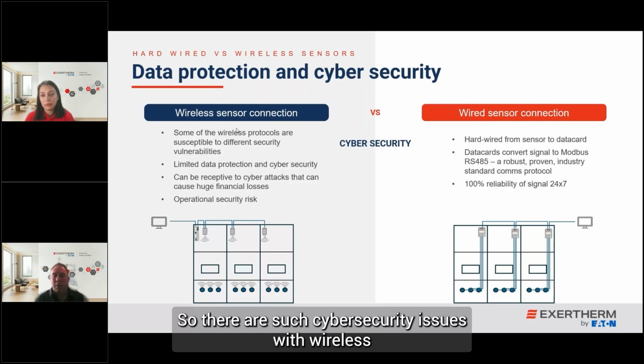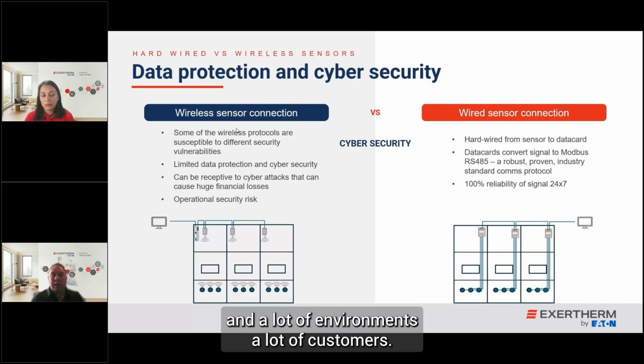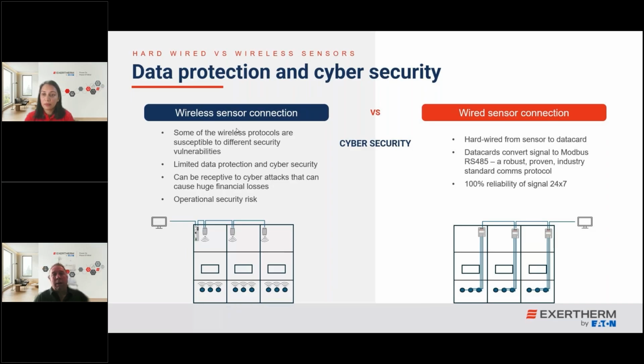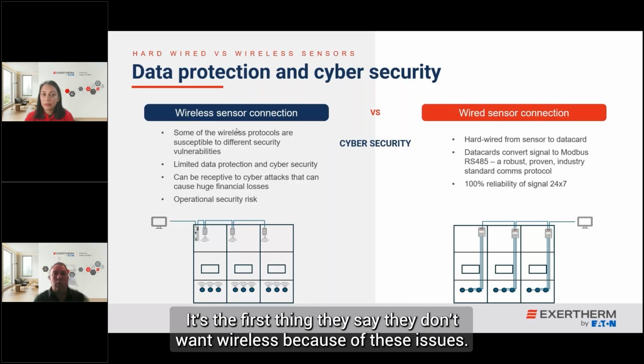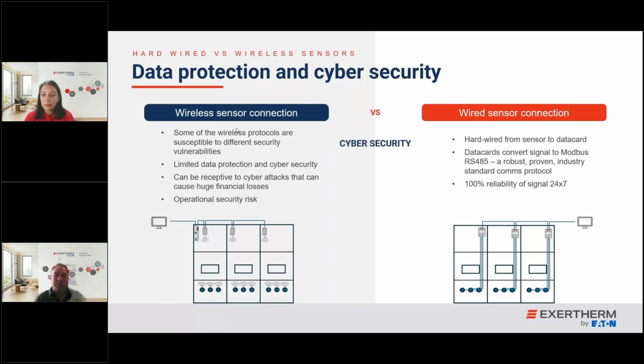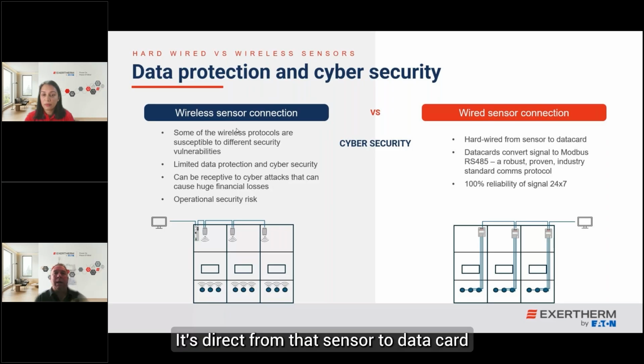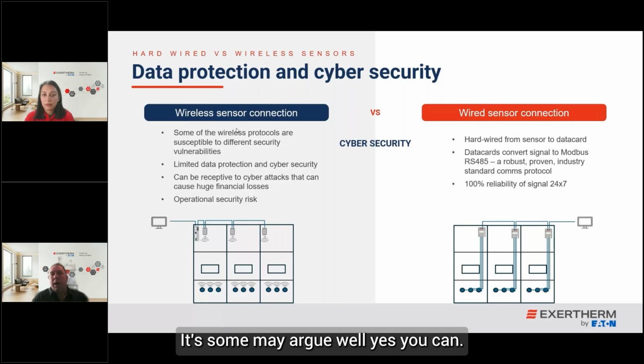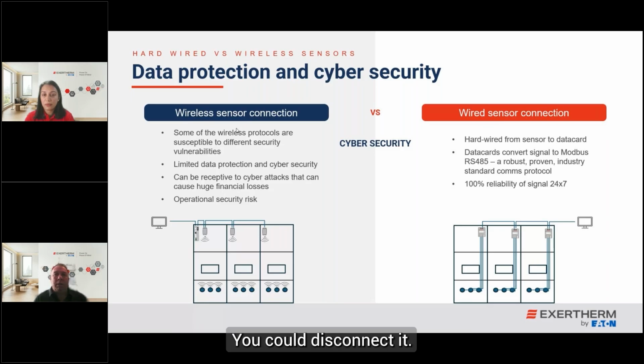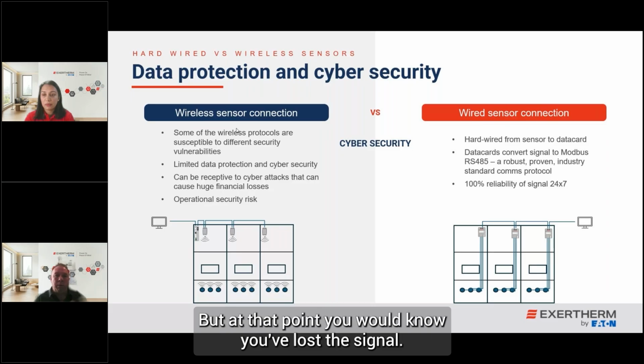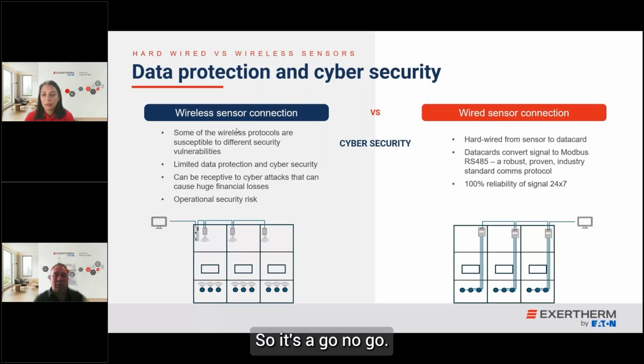You don't know. So there are cybersecurity issues with wireless, and for a lot of environments and customers, that's the first thing they say—they don't want wireless because of these issues. Hardwired is direct from that sensor to the data card. You can't interfere with it. Some may argue, well, you could disconnect it or cut the cable, but at that point you would know you've lost the signal. So it's a go, no go.